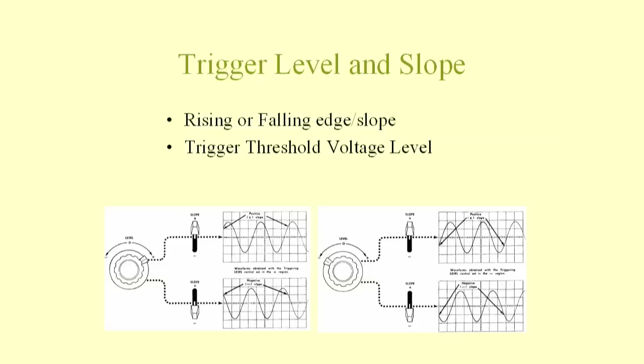That's set by this. If I adjust that threshold down, then I'm triggering because it's coming up through that voltage down here. So that's essentially adjusting a threshold, to say when that voltage reaches that threshold, that's when I want to shoot the sweep across. The slope, positive or negative, says which way I'm approaching that threshold to cross it. Am I approaching it from the bottom and crossing it going positive? That's the positive slope. Or am I approaching that voltage threshold coming down, and I want to trigger when I go down below that threshold?